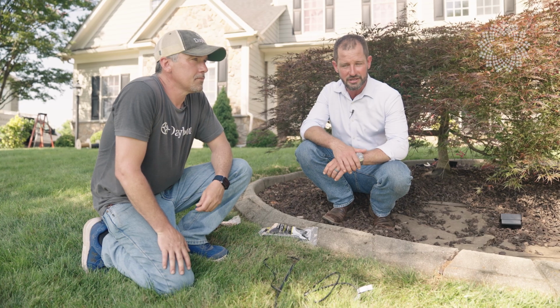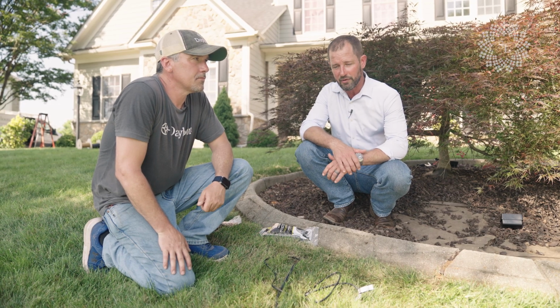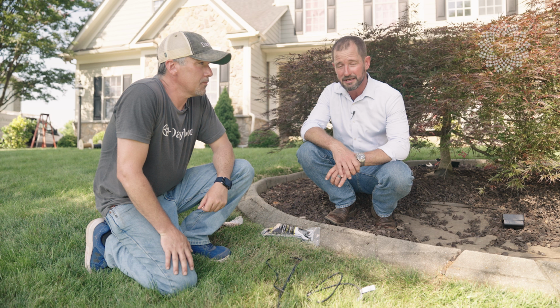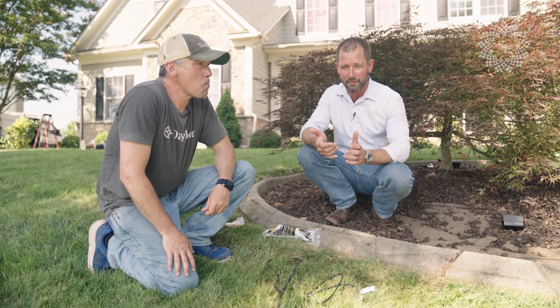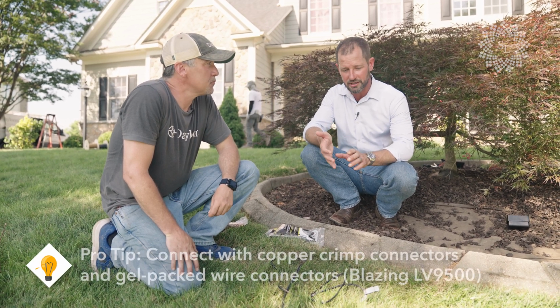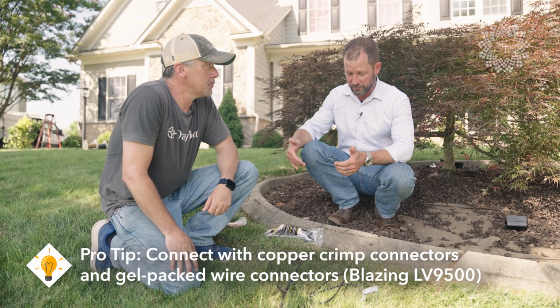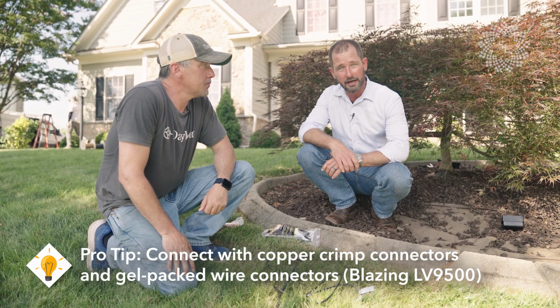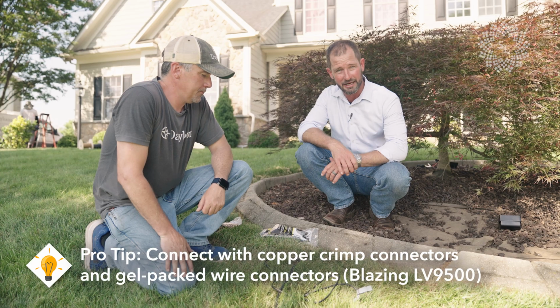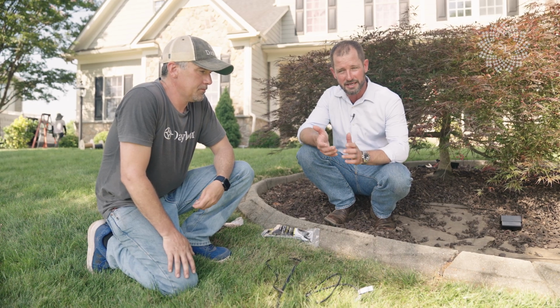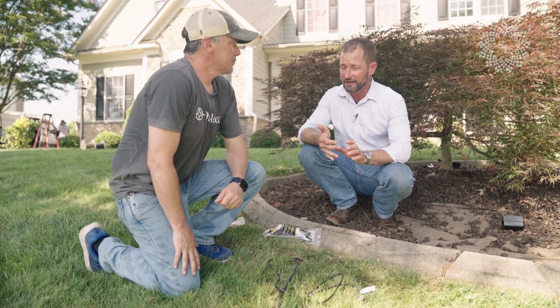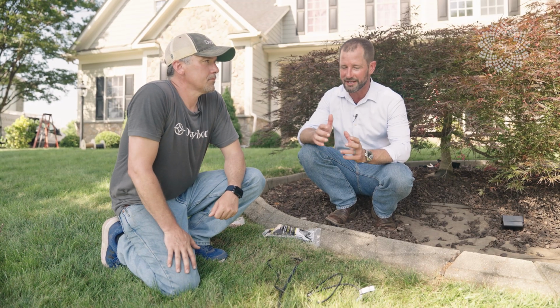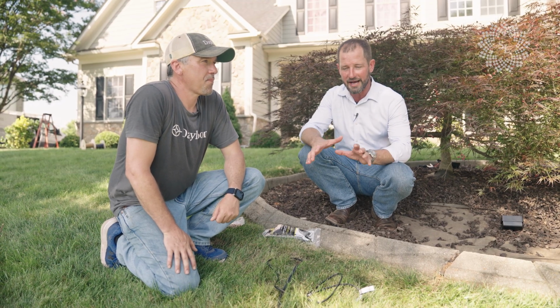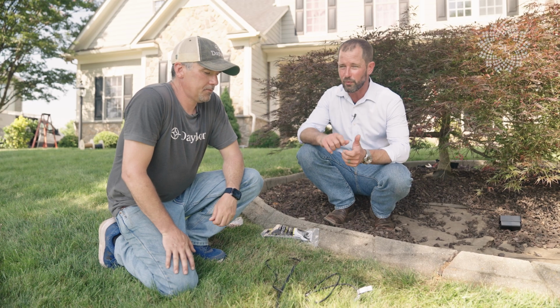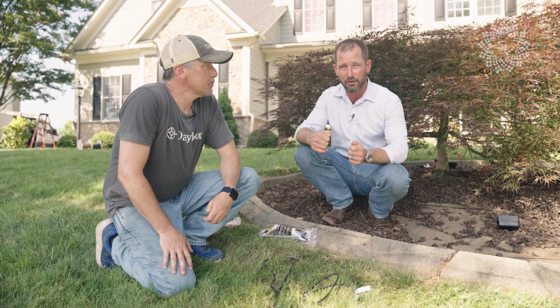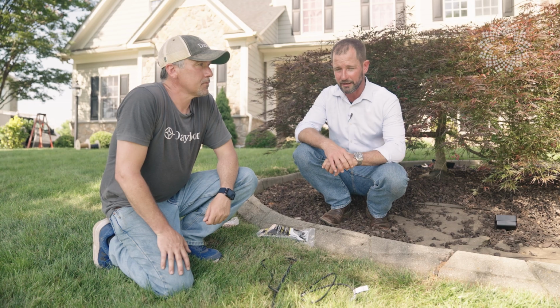We designed our own connection system many years ago, and we've been using it for at least 15 years. The only two connections I really recommend are a heat shrink connection, which is permanent, or the connection we're doing with a crimp and our gel-packed connector system. We use the Blazing LV 9500. Those are the two I like best. We've done soldered connections, tube connections with smelly grease, and a lot of other types. I don't like wire nuts. The gel pack wire nuts tend to not hold pressure, come loose, corrode, and let moisture in more.